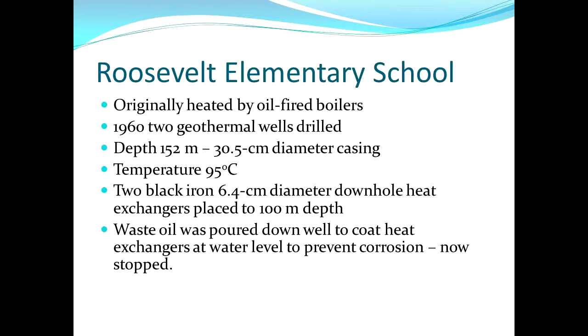The depth of this well was only 152 meters, with 95 degree centigrade water—we do have really hot water in our area. They use a downhole heat exchanger to pull that water up; we're not pumping the water out. All we're doing is running a black iron pipe down the well. It's a closed loop system, and all we're doing is extracting the heat.